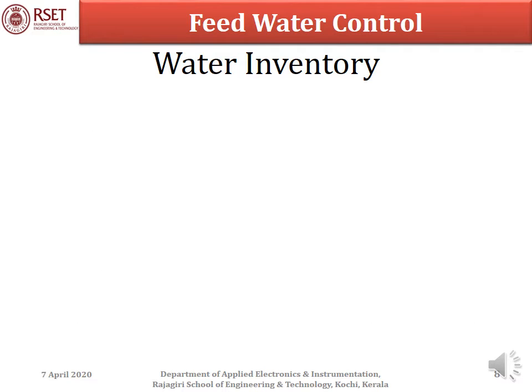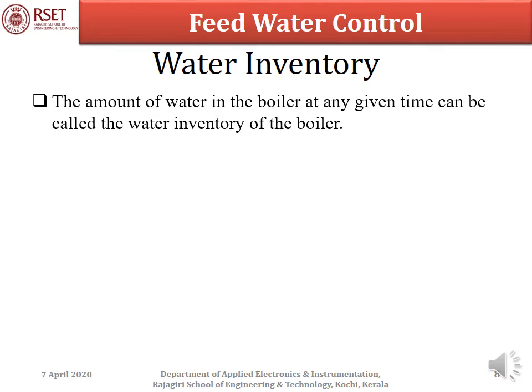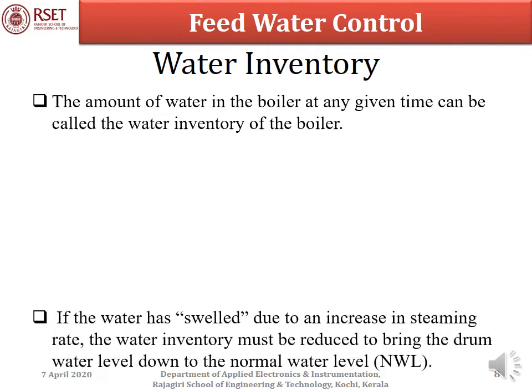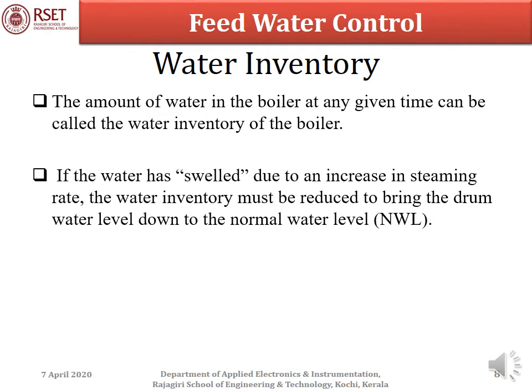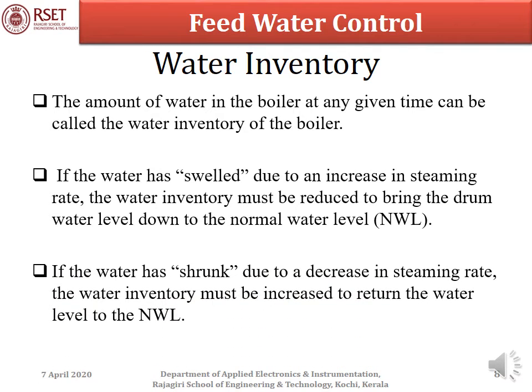The amount of water in the boiler at any given time is called the water inventory of the boiler. If the water has swelled due to an increase in steaming rate, the water inventory must be reduced to bring drum water level down to normal water level. If the water has shrunk due to a decrease in steaming rate, the water inventory must be increased to return the water level to NWL.